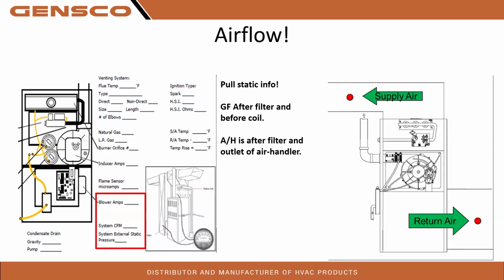So on a gas furnace, the manufacturer doesn't know what coil is going to go on it. So we're always just going to go across the furnace itself. And in this example picture, there is no coil. So we're simply going to go return air after the filter, and then we're going to go the supply air after the furnace. The factory actually pulls them after the filter and then at the high limit. That's okay to do even with a coil on top, right? So if that is easier, do it that way.